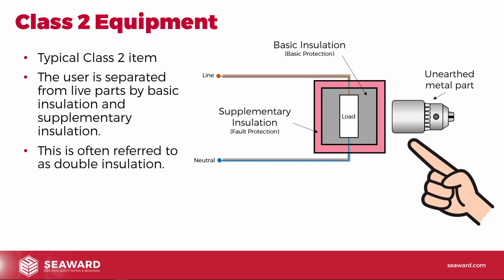This is often referred to as double insulation. You might hear people talk about double insulated equipment, the protective measure, double or reinforced insulation. And it's just a different strategy for doing it. Quite often this is seen, as I mentioned earlier, as being safer.